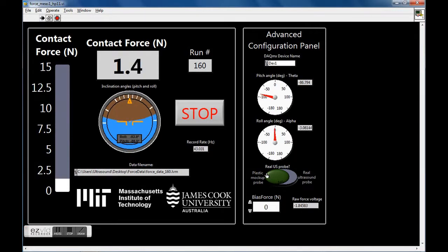Alright, so now when you're just about ready to conduct an exam, hold the probe in the air and note what the contact force reads. In this case, reading about 1.4 newtons. So go ahead and type that 1.4 newtons into the bias force box right here. So type 1.4 and press enter. And now you'll notice that the contact force fluctuates around 0, which is what we want. So if you press on the ultrasound transducer, you'll see the force go up and go down.